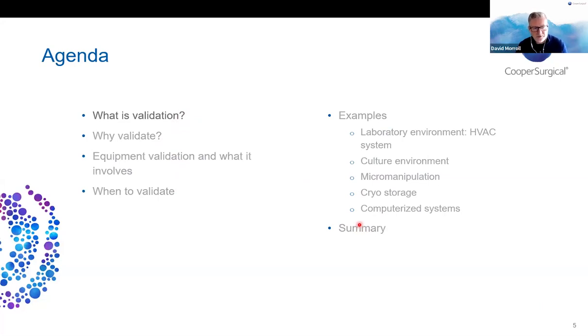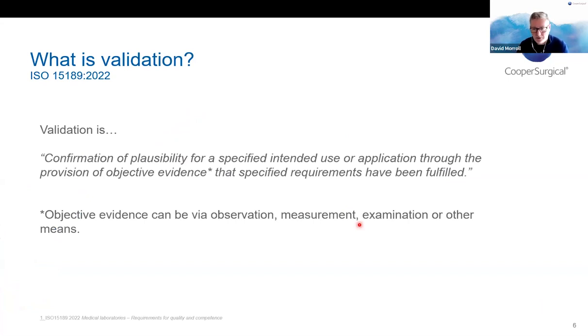So let's take a quick look at what validation is, and you can look around for various technical descriptions of it, but essentially it's confirmation of plausibility for a specified intended use or application through the provision of objective evidence that specified requirements have been fulfilled, and that's taken directly from the ISO 15189 standards for medical laboratories. And what it means is when you validate, you set out what the intended use is, the specifications that a particular piece of equipment needs to meet, and then of course the objective evidence is based on testing, measuring and making sure those specifications are met.